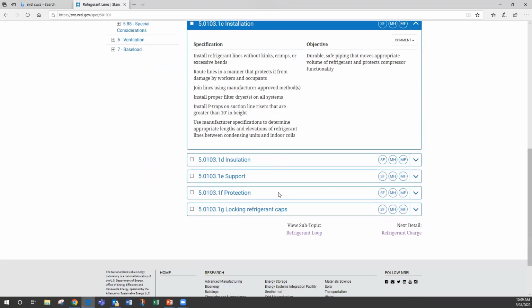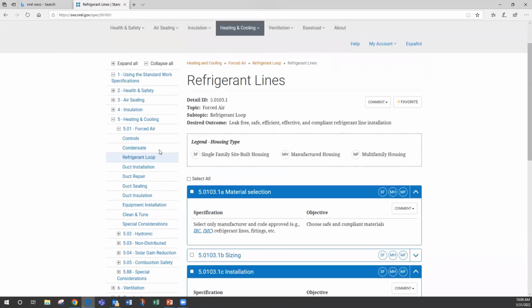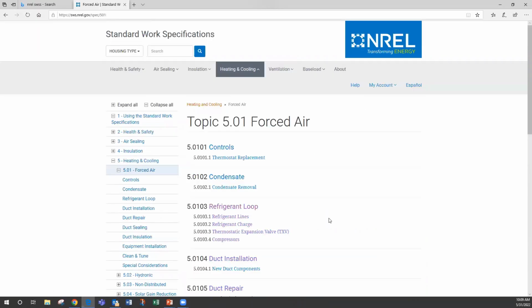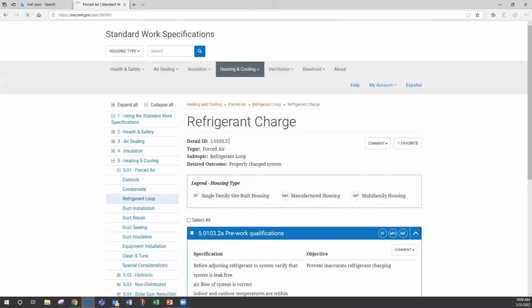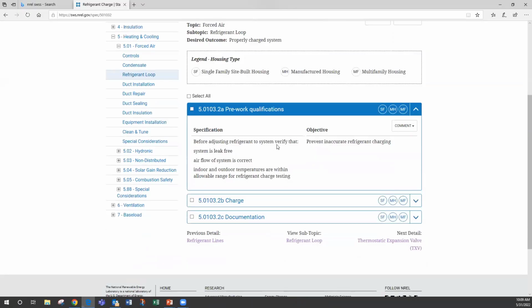So your HVAC contractors are going to want to dig into this just to make sure that they understand what the desired outcome is based on the SWS. Let's go back here. So let's look at refrigerant charge then. Under refrigerant charge, before adjusting the refrigerant system, verify the system is leak-free and the airflow of the system is correct. And this is one that often gets overlooked by HVAC contractors, or they fail to do it, and that is verifying that you have 400 CFM per ton of equipment at your fan coil. The newer equipment might be as low as 350, but 400 CFM per ton. If you do not verify that airflow before you start to do a refrigerant charge based on superheat and subcooling, you will not get the correct charge.